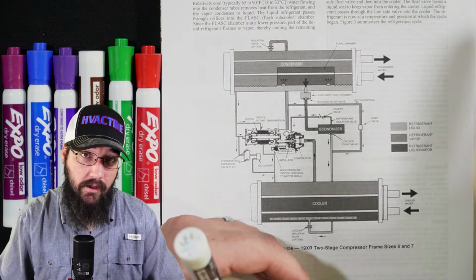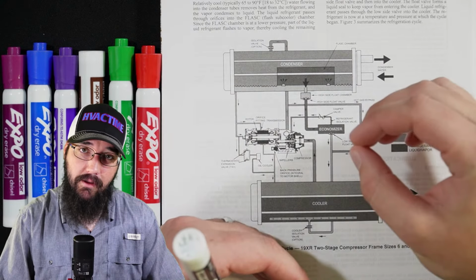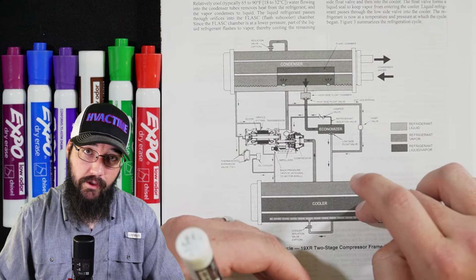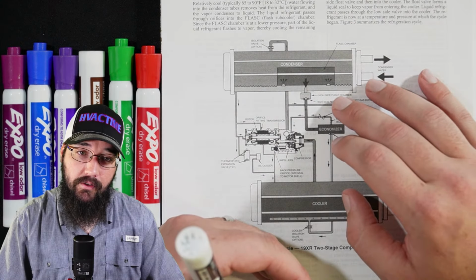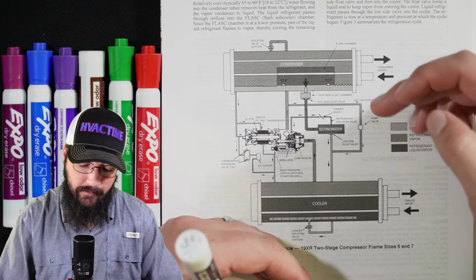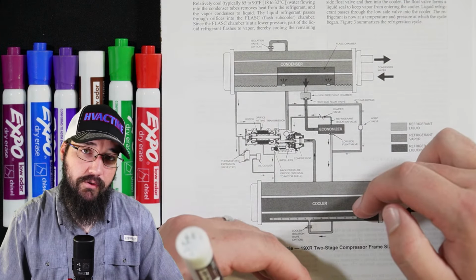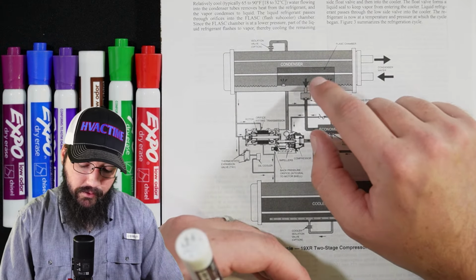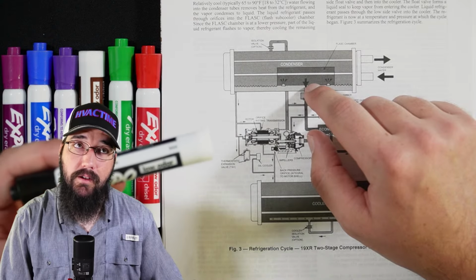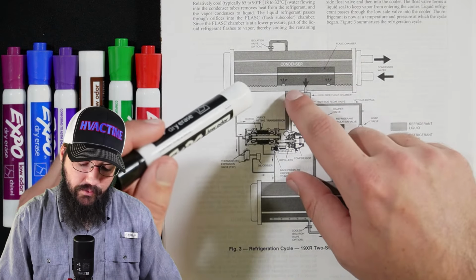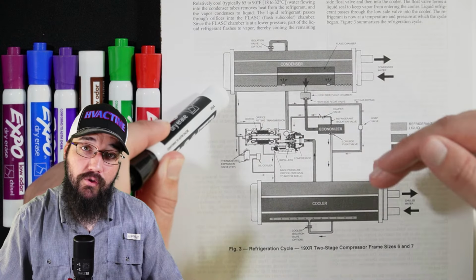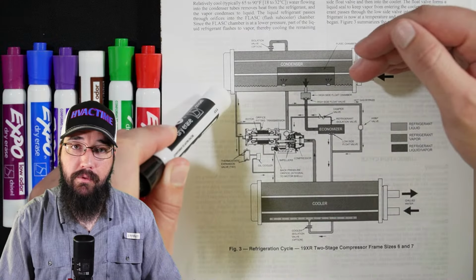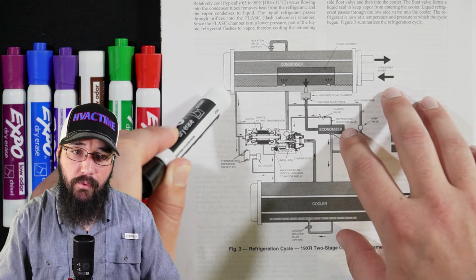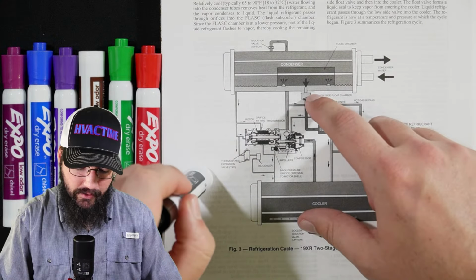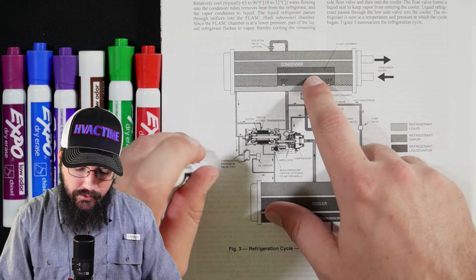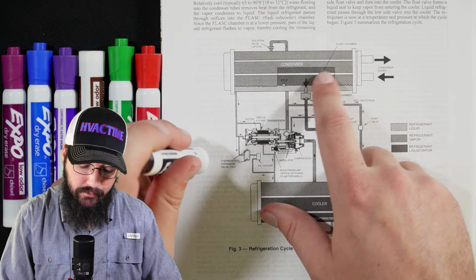Now medium pressure could mean a lot of things. The core of how to define a medium pressure is it is in between our high and low pressure, but it's still an intentional part of the operating circuit. With a normal refrigerant circuit, we're just going from high pressure to low pressure through the metering valve, and that's it. But when we start dealing with tanks like this, or these types of economizing chambers, that's when we start dealing with intentional medium pressures, where we're not going from one extreme to the other immediately. We're actually entering into this mid zone, but it's still part of the design. It's not on accident.